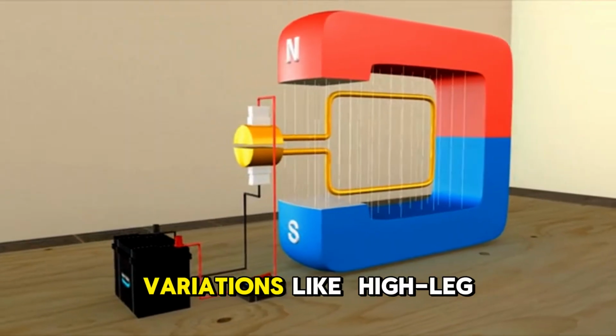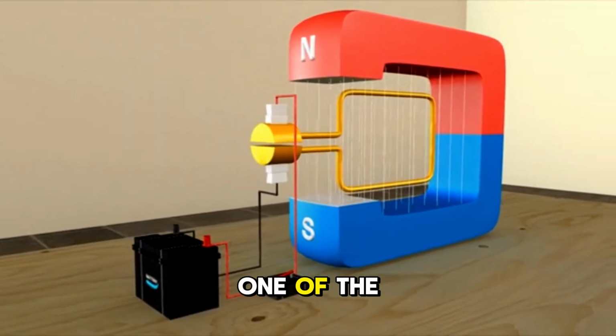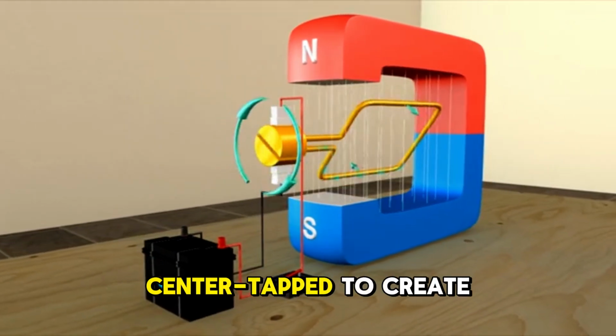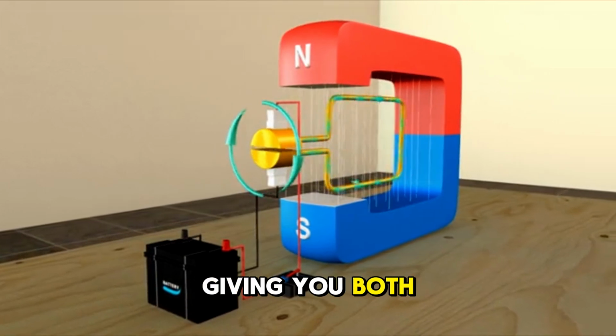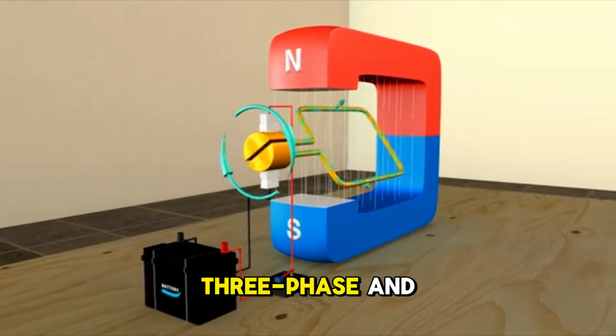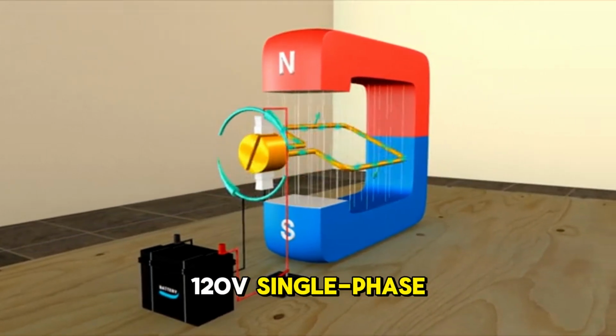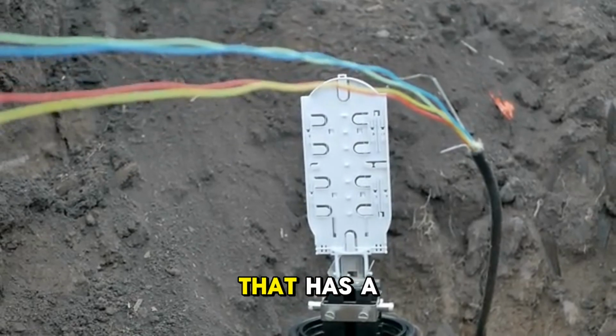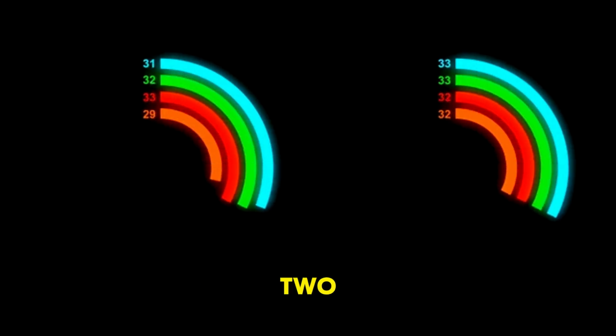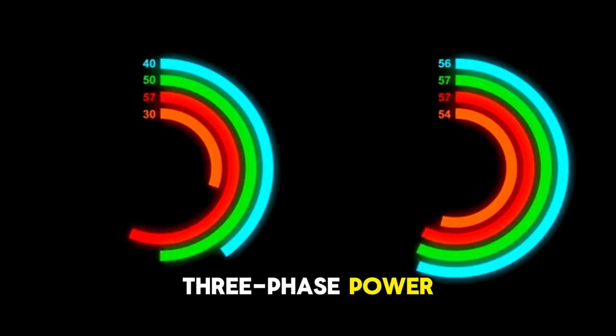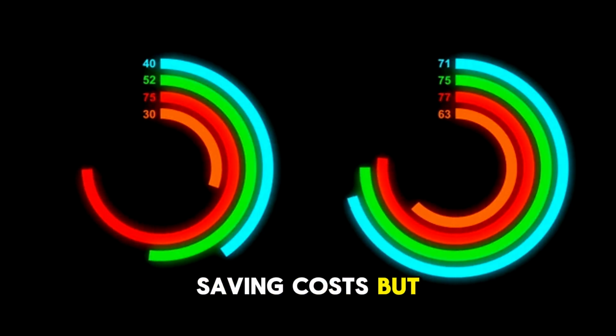There are also variations like high leg delta, where one of the delta coils is center tapped to create a neutral, giving you both 240 volts three-phase and 120 volts single-phase, but with one high leg that has a higher voltage to ground.